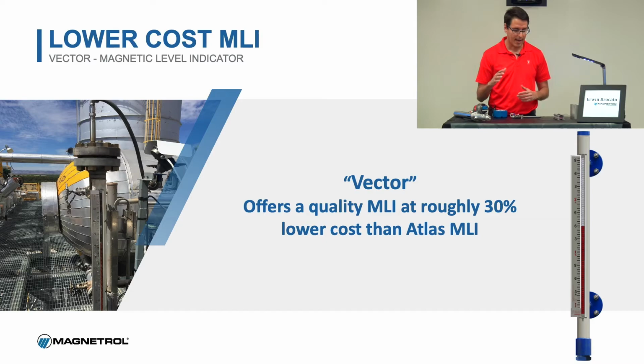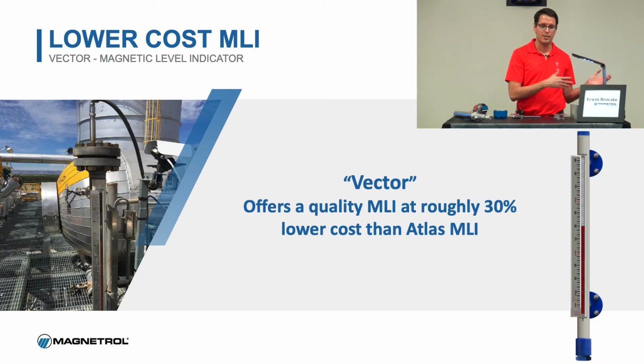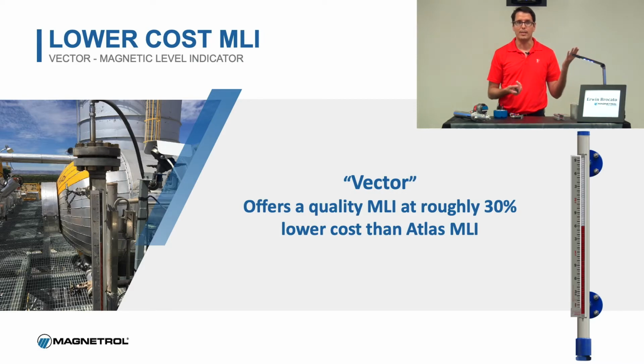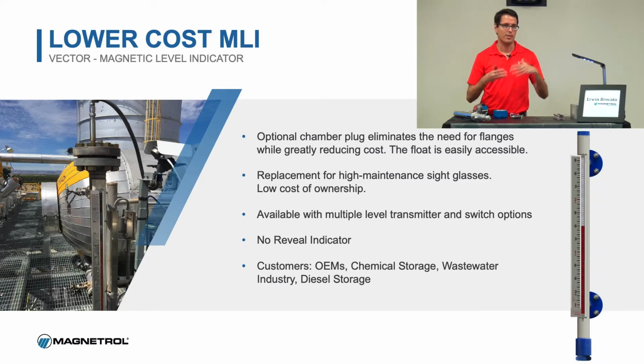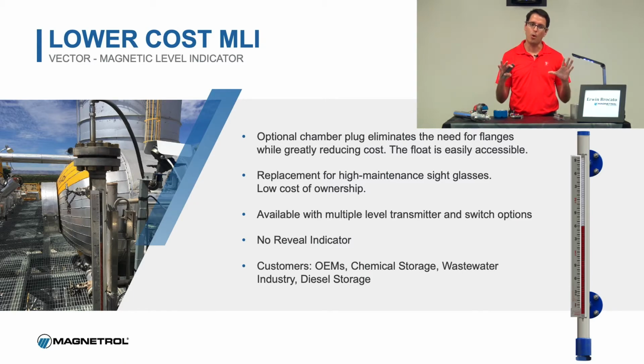On the low cost side for the magnetic level indicators, we have the Vector. The Vector is just a brand name. We have different brand names for our different products. The other one you see on here is the Atlas. That's the higher end model. The Vector has certain limitations, not as many variations, and a simpler flag rail indicator versus our Atlas indicator. We also use carbon steel for a lot of the process connections. We try to eliminate flanges wherever we can and just use NPT connections in order to bring the cost down for this particular product. But it's still a high quality product. The float that goes inside is as good as a float that would go into an Atlas product. But again, we have limitations on what the device can withstand as far as pressure and temperature, just like the other products we've been talking about. Less configurations, no specials, but same quality, lower cost.